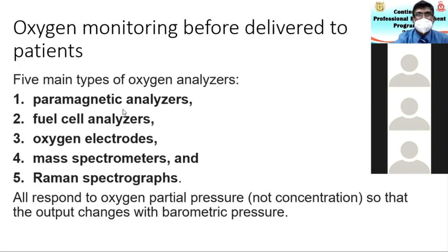These are the oxygen analyzers: paramagnetic oxygen analyzer, fuel cell oxygen analyzer, oxygen electrodes, mass spectrometer, Raman spectrograph. They all respond to oxygen partial pressure, not concentration, therefore the output changes with barometric pressure.